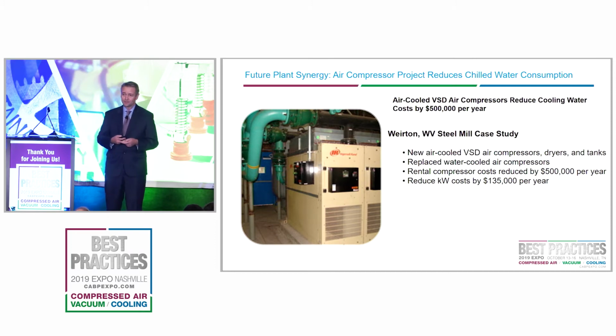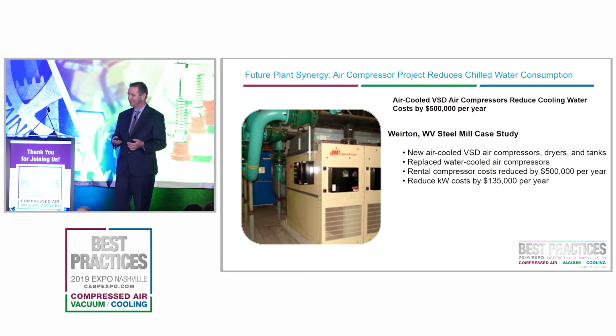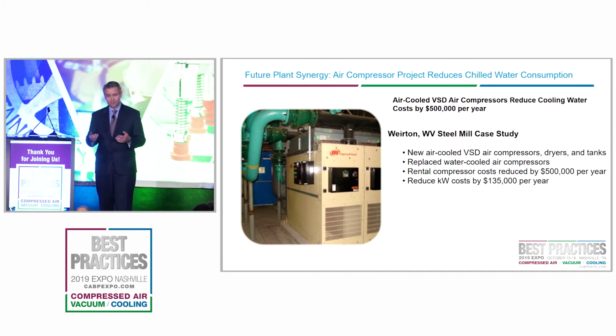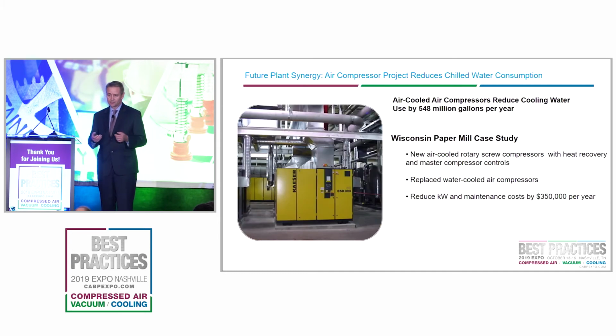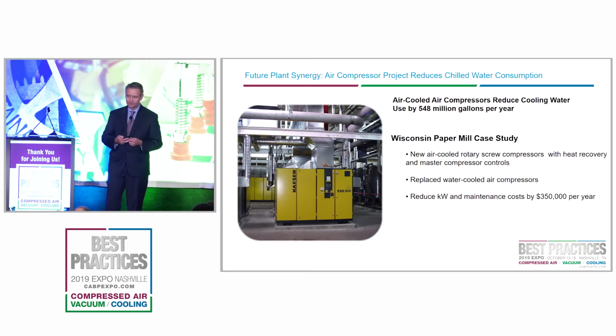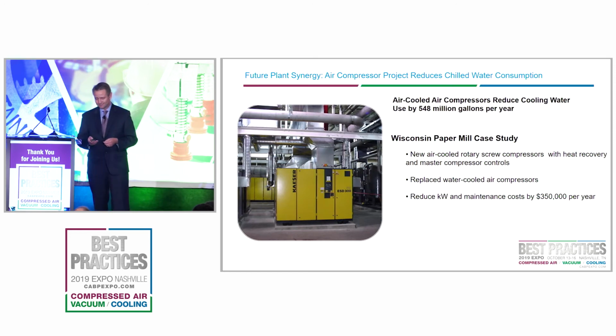But the biggest benefit was cooling water, and we don't even have cooling water treatment numbers or chemicals included here. So that's an air-cooled, water-cooled dynamic, and you've got to be very careful with that. Let's examine a similar case study: a Wisconsin paper mill with water-cooled older recips going to air-cooled, in a climate-controlled compressor room, saved 548 million gallons per year. For me, that's a staggering amount of water. KW and maintenance costs saved $350,000 - these are big numbers. For me, the theme here is water-cooled versus air-cooled on these slides.